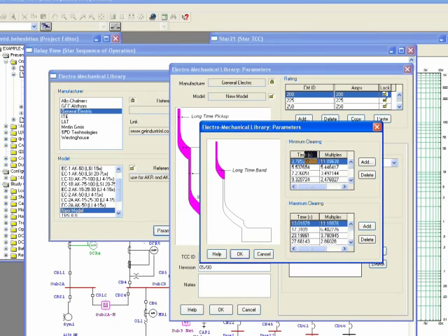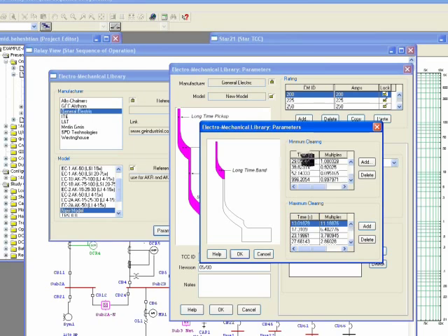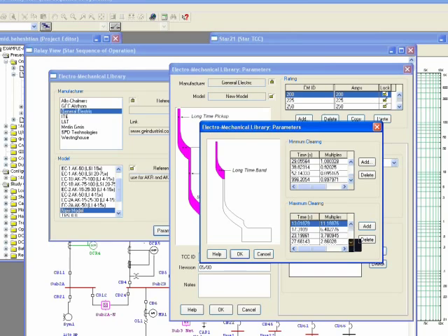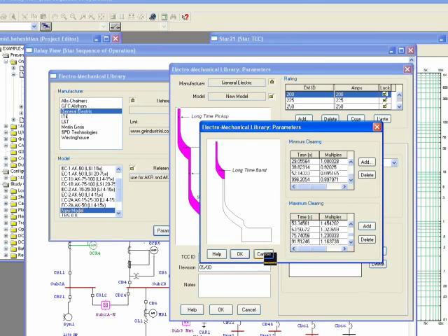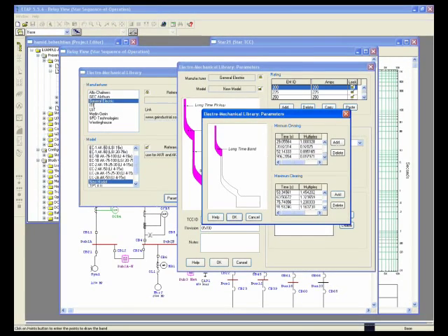And enter the curve point, same concept as fuse time versus current for minimum melting, for maximum clearing time versus current. You can enter it here in this table. Let me show you a sample.